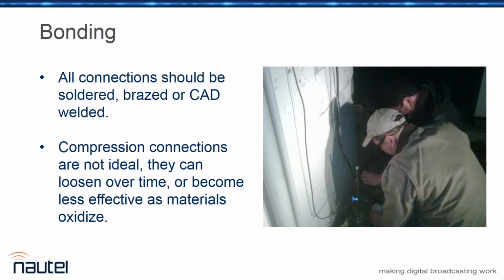Yeah, and what happens with copper? Copper's malleable, a soft metal, so as it's compressed it attempts to flow and displace the air within the connection. Especially with stranded wire, you're never going to displace all the air unless you're using a $1,000 or $500 crimp tool, depending where you buy it. So copper connections with any kind of compression connection will tend to get loose.